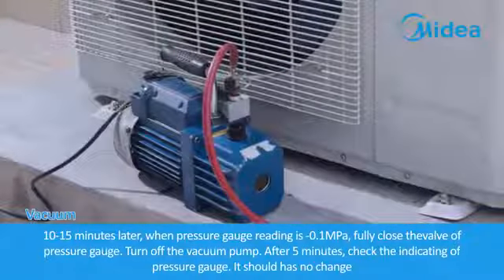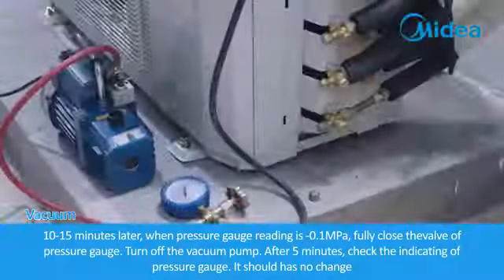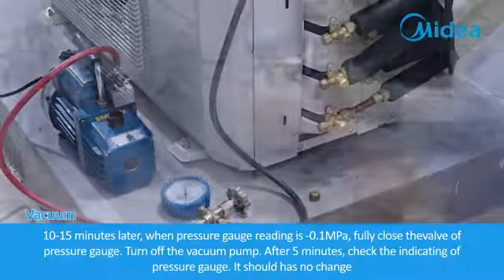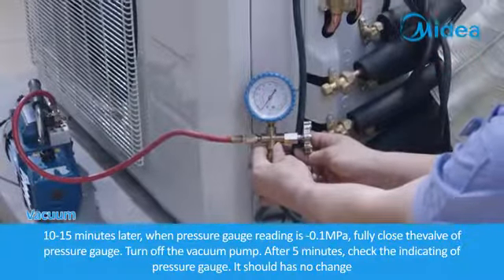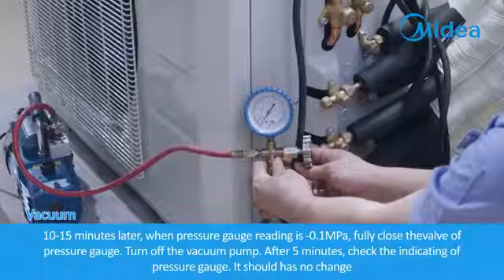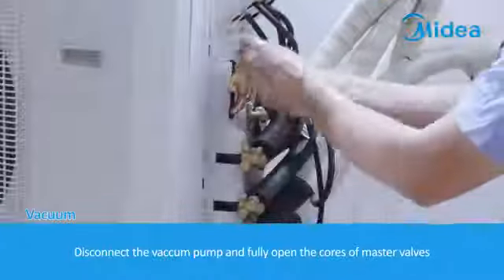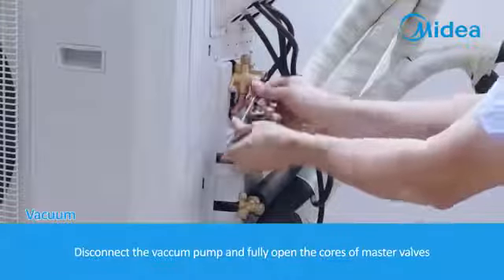Turn off the vacuum pump. After 5 minutes, check the indicating of pressure gauge. It should have no change. Disconnect the vacuum pump and fully open the cores of master valves.